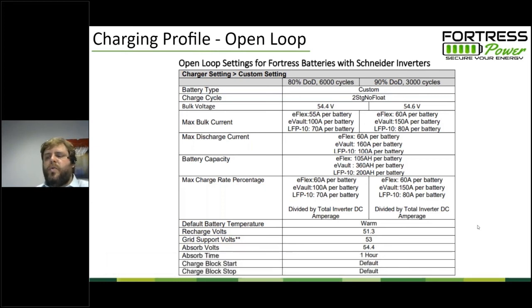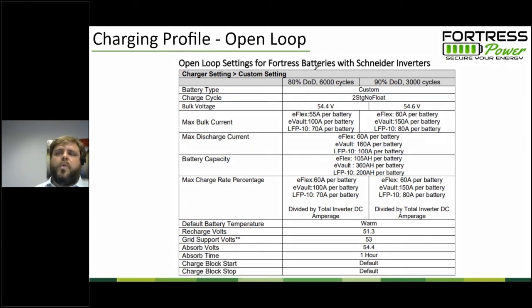And so it's very hard to say what the state of charge of the battery is when you're just measuring voltage and not doing computer-based tracking of every single statistic about the battery to compute a state of charge. With open loop programming, we're basically saying voltage-controlled programming, and you're programming setting by setting. Now these settings should not differ from one inverter to the next if the inverters are similarly sized. There may be a slight nuance or terminology difference that comes out of our testing, where we say, oh, this inverter charges slightly harder than the others. So you might see a slight difference between one or the other, nothing that's going to be a deal breaker. By and large, we're saying program at 54.4 volts for your charging. Set your absorb time equal to 1 hour.